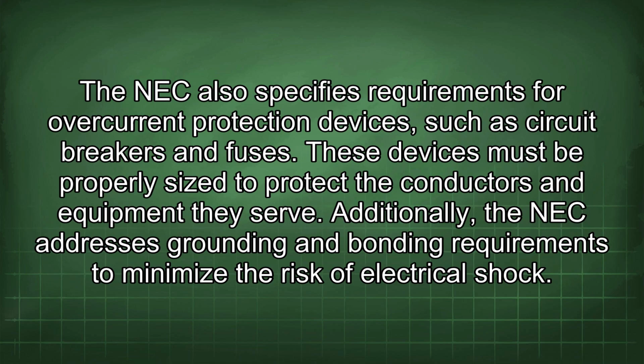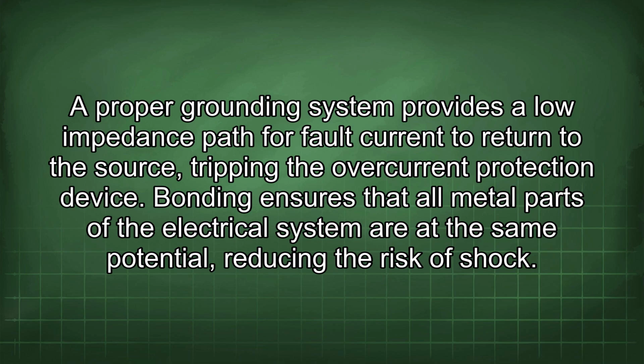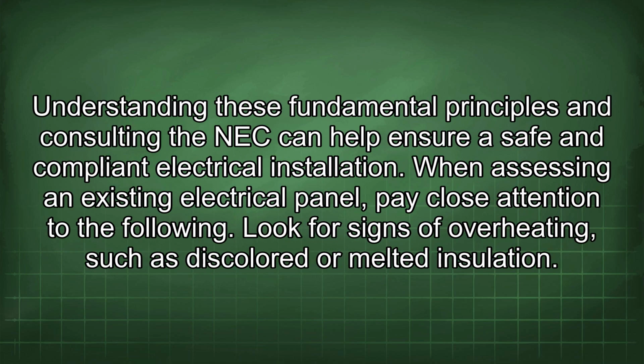The NEC also specifies requirements for overcurrent protection devices, such as circuit breakers and fuses. These devices must be properly sized to protect the conductors and equipment they serve. Additionally, the NEC addresses grounding and bonding requirements to minimize the risk of electrical shock. A proper grounding system provides a low impedance path for fault current to return to the source, tripping the overcurrent protection device. Bonding ensures that all metal parts of the electrical system are at the same potential, reducing the risk of shock. Understanding these fundamental principles and consulting the NEC can help ensure safe and compliant electrical installation.